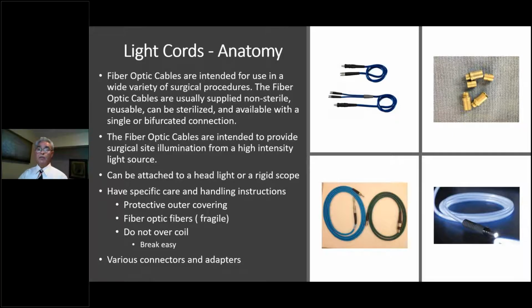There are a variety of these out there, and hopefully every hospital has a different manufacturer for the surgical instrument, so you have different light cords and different adapters, and you want to make sure you have the appropriate adapters. As you saw from the previous photo, the fiber optic glass, when they get burned, you're going to have damaged fiber optic reducing the light source to the end of the cord. Usually they say if you have about 80% light that's good, but anything below that, you need to probably replace the light source.